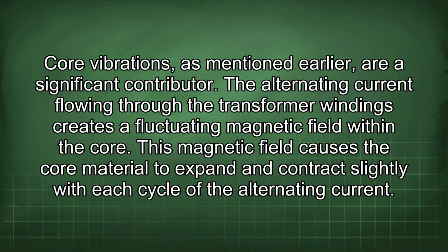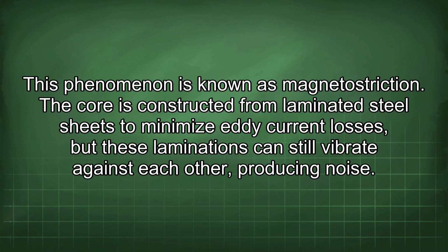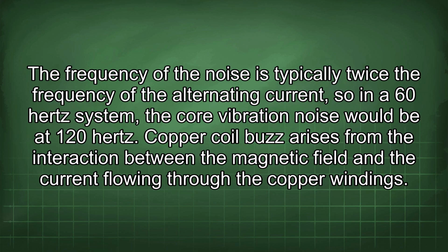Core vibrations, as mentioned earlier, are a significant contributor. The alternating current flowing through the transformer windings creates a fluctuating magnetic field within the core. This magnetic field causes the core material to expand and contract slightly with each cycle of the alternating current. This phenomenon is known as magnetostriction. The core is constructed from laminated steel sheets to minimize eddy current losses, but these laminations can still vibrate against each other, producing noise. The frequency of the noise is typically twice the frequency of the alternating current, so in a 60 Hz system, the core vibration noise would be at 120 Hz.